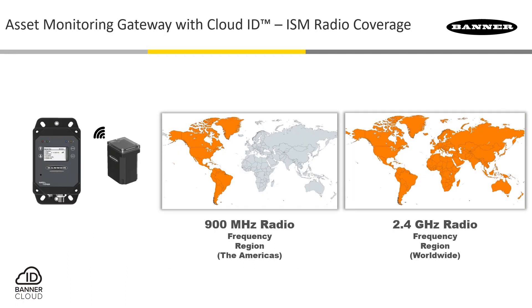The next decision to complete for the gateway is the selection of the ISM frequency used by the radio module within the devices. The radio provides the backbone of the local wireless network that you'll create as you configure these systems. A 9 in the model number will indicate 900 MHz frequency range, and a 2 indicates a 2.4 GHz frequency range.